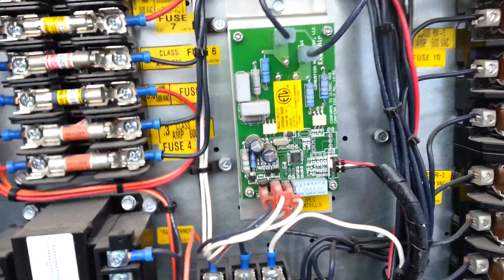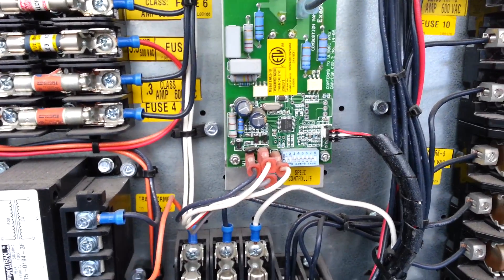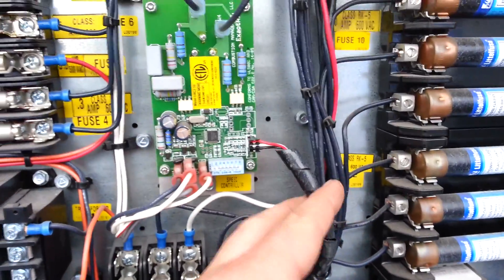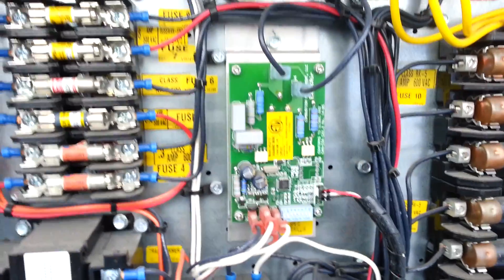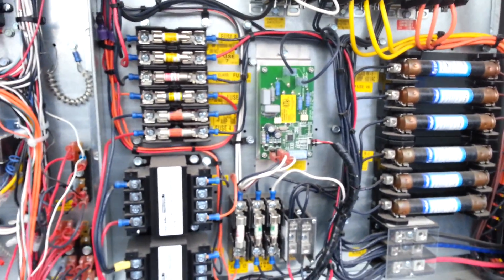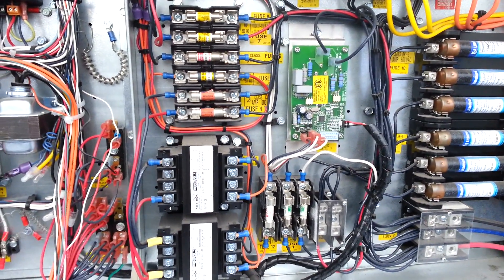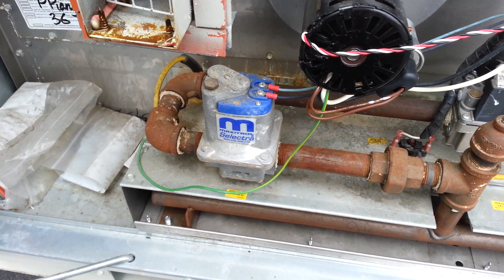This particular unit has one of these fan speed controllers, and here's the tachometer wires from the motor, from the Hall-effect sensor. It's modulating that combustion blower motor as it modulates the gas valve. There's the Maxitrol modulating gas valve right there.